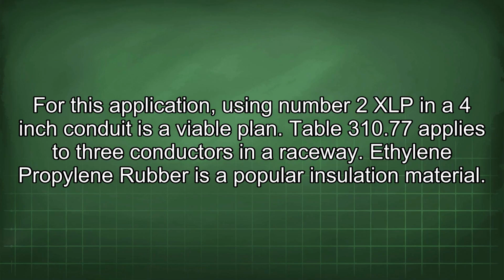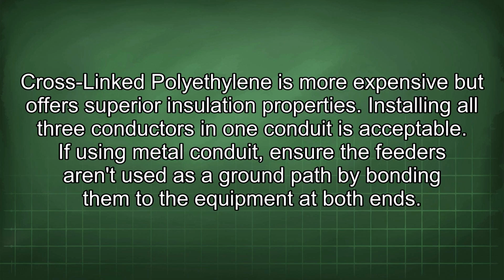For this application, using number 2 XLP in a 4-inch conduit is a viable plan. Table 310.77 applies to 3 conductors in a raceway. Ethylene-propylene rubber is a popular insulation material. Cross-linked polyethylene is more expensive but offers superior insulation properties. Installing all 3 conductors in one conduit is acceptable.